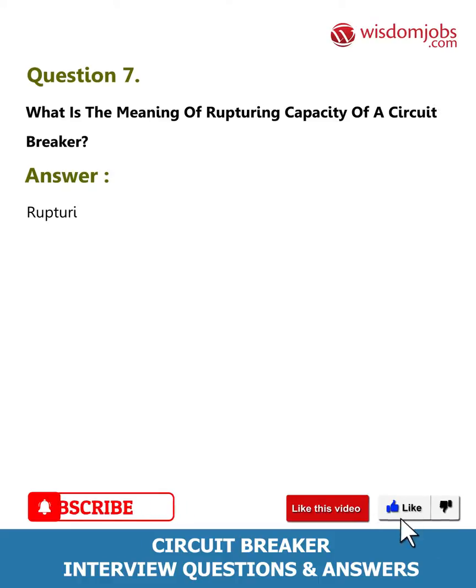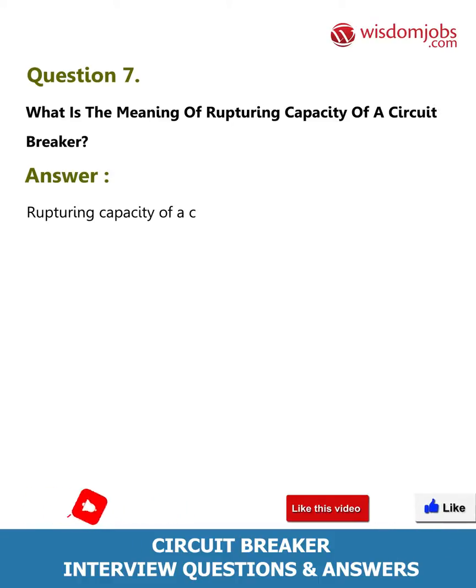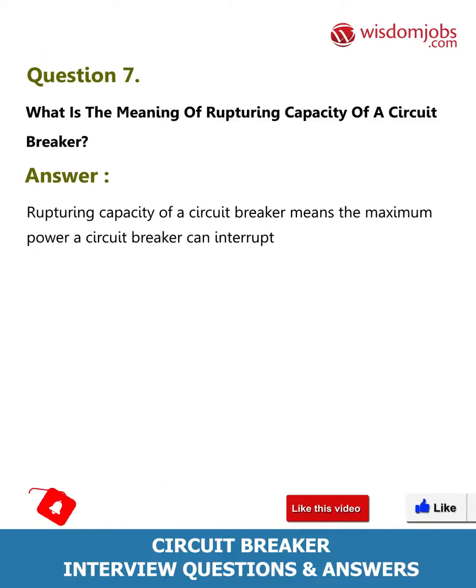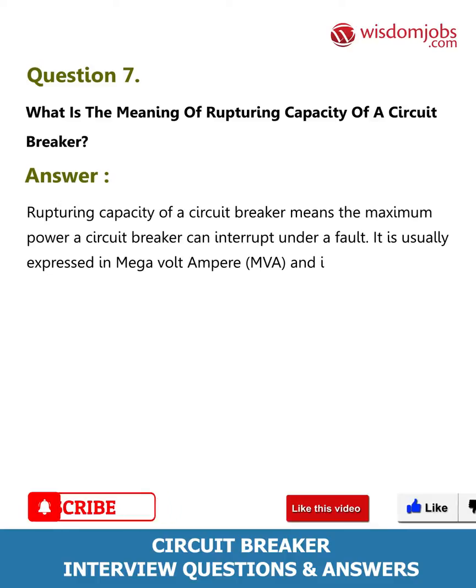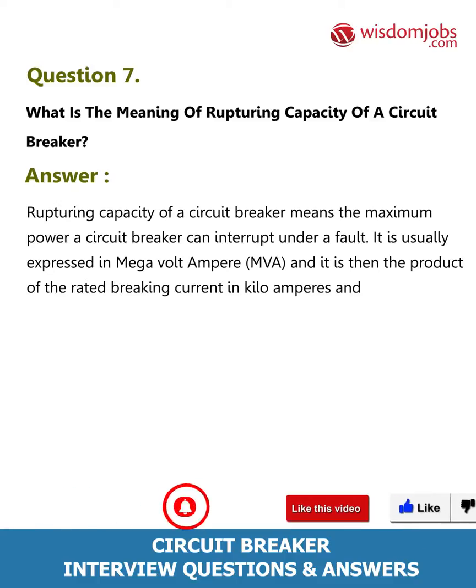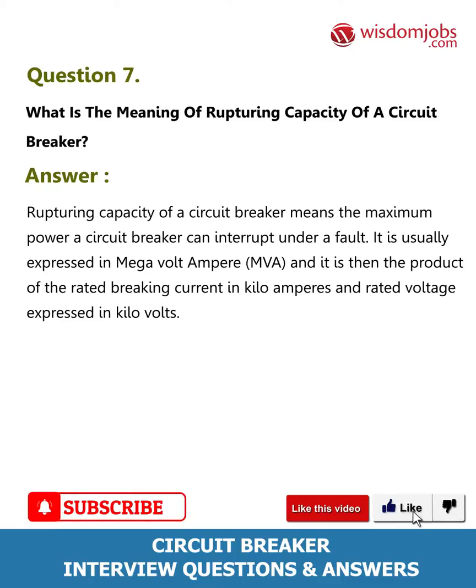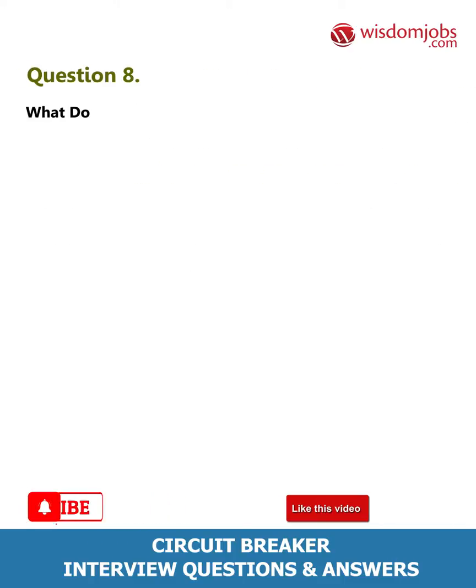Question 7: What is the meaning of rupturing capacity of a circuit breaker? Answer: The rupturing capacity means the maximum power a circuit breaker can interrupt under a fault. It is usually expressed in megavolt amperes (MVA) and is the product of the rated breaking current in kiloamperes and rated voltage in kilovolts. Question 8: What do you mean by the making current and breaking current of a circuit breaker?